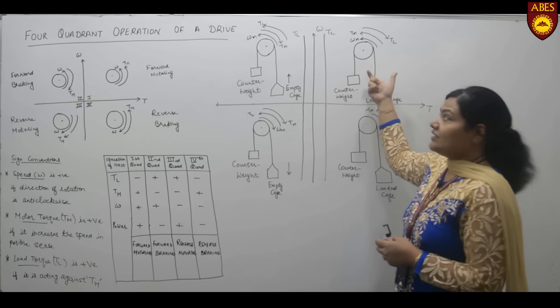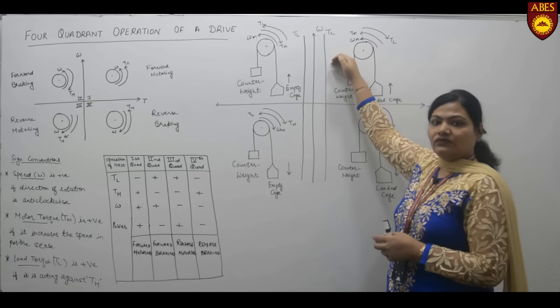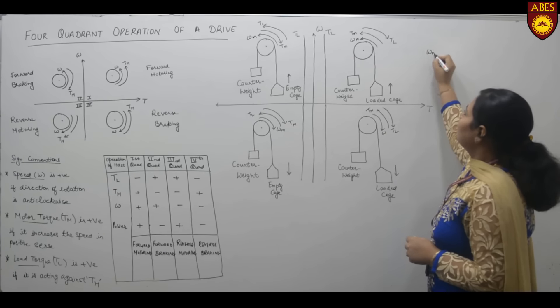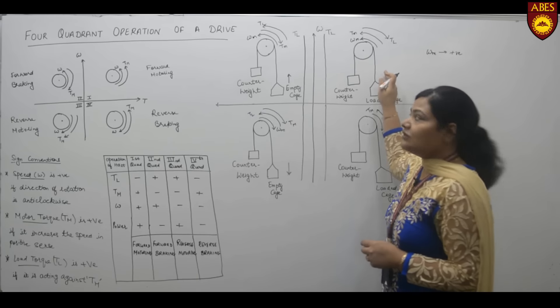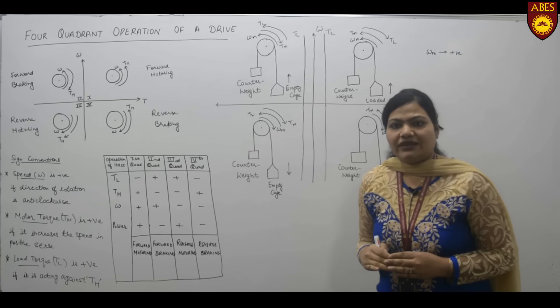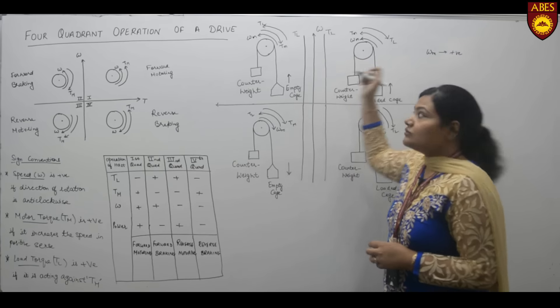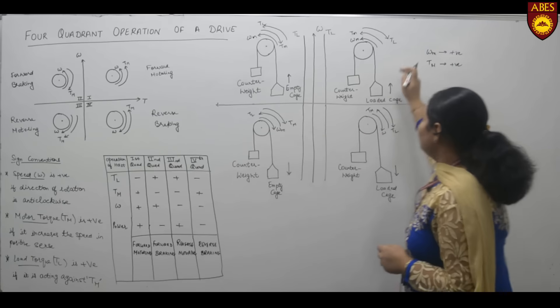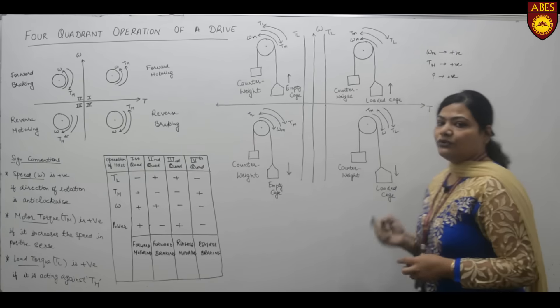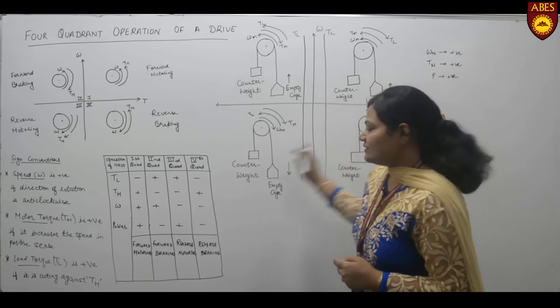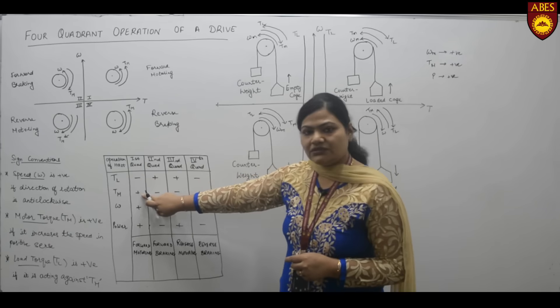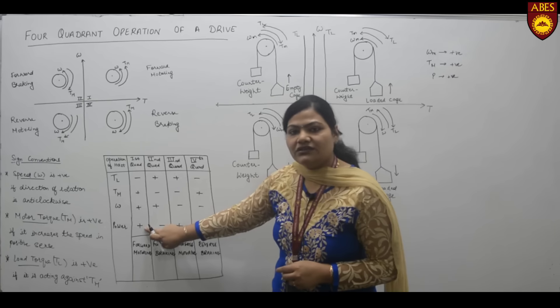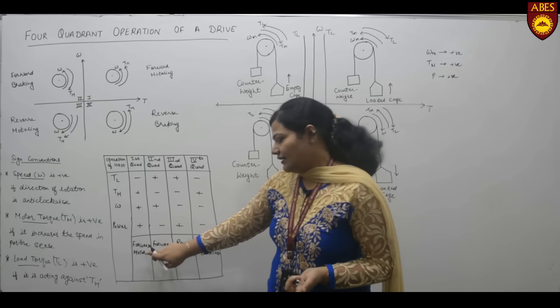In the first quadrant, the motor is hoisting up the loaded cage and must run in the anticlockwise direction, so omega m is positive. To lift the loaded cage, the motor torque must assist the speed of rotation, so Tm is also in the anticlockwise direction, making it positive. Power is positive. According to the table, Tl is negative, motor torque is positive, and speed is positive. Power, omega times Tm, is positive, and because rotation is anticlockwise, this is the forward motoring mode.